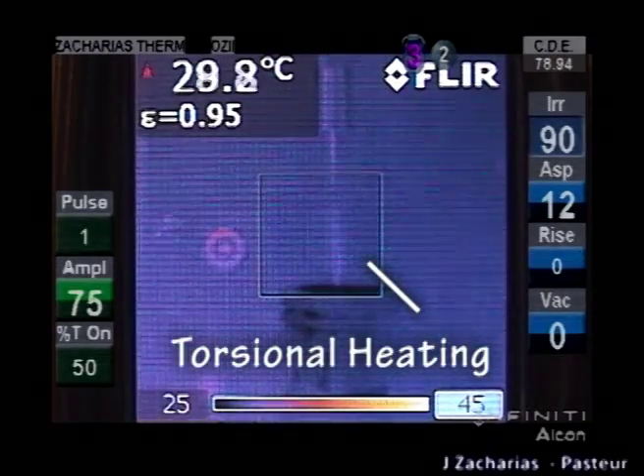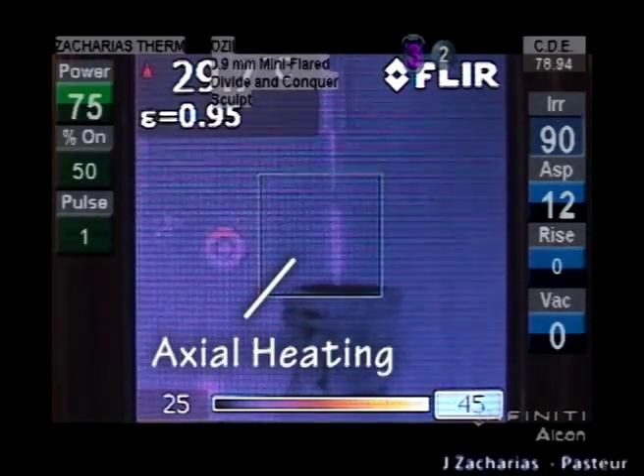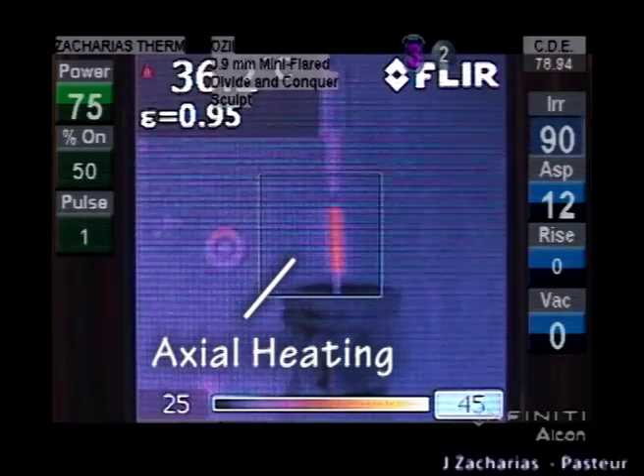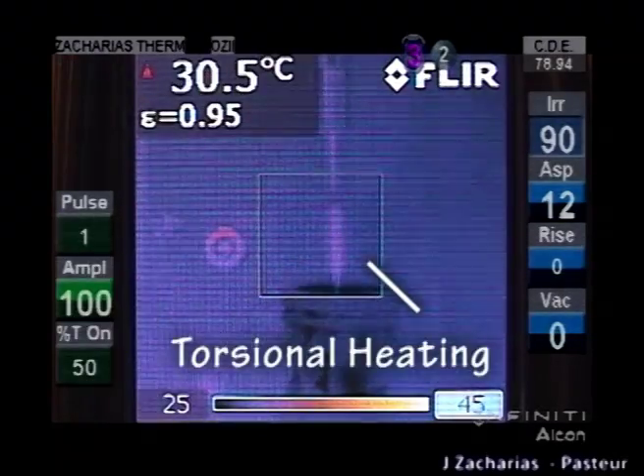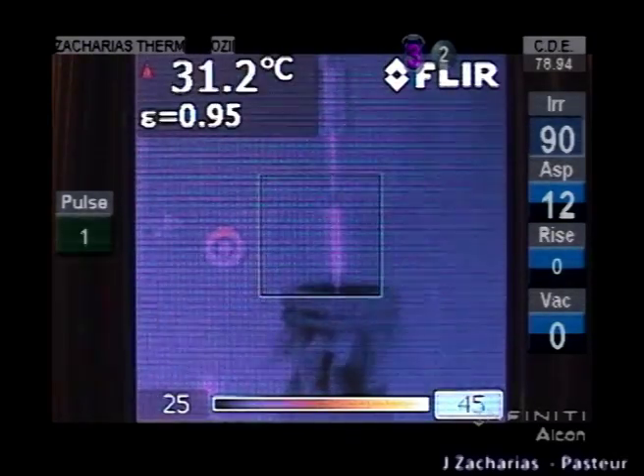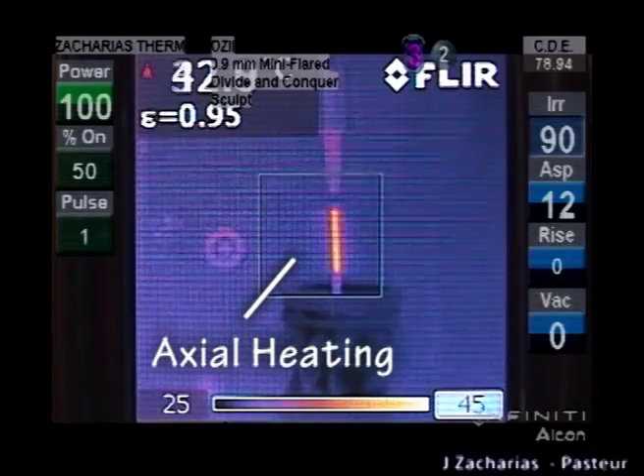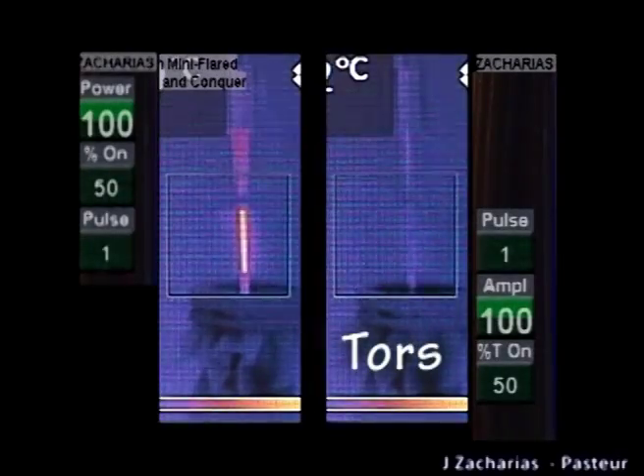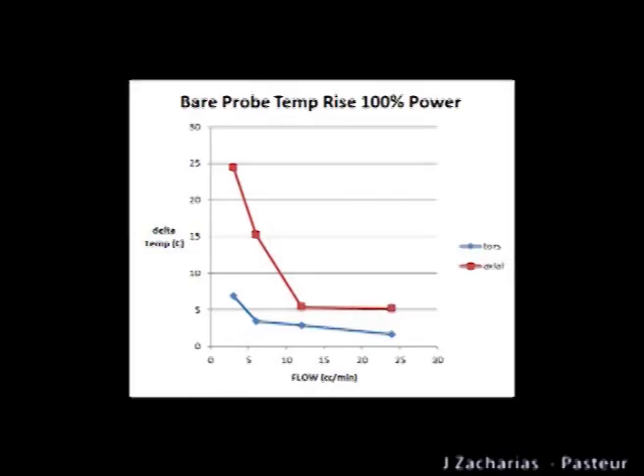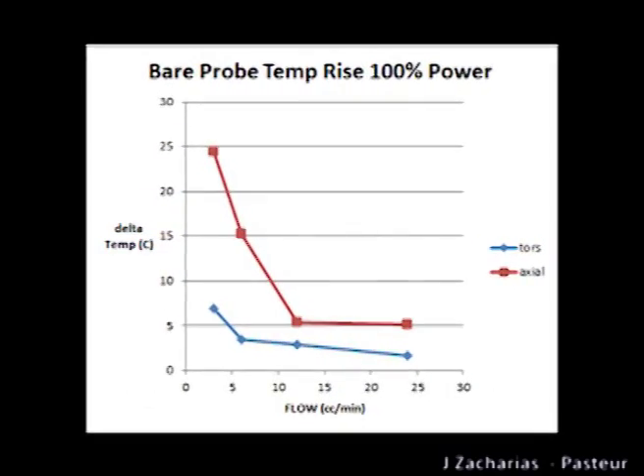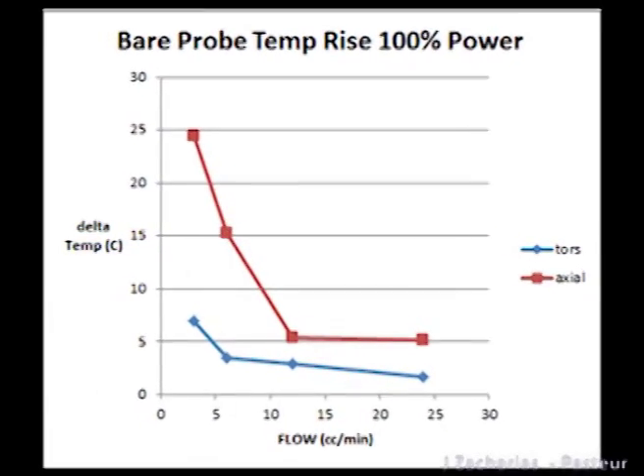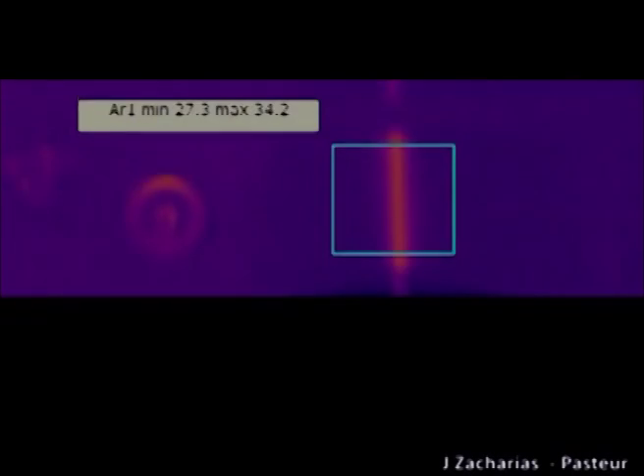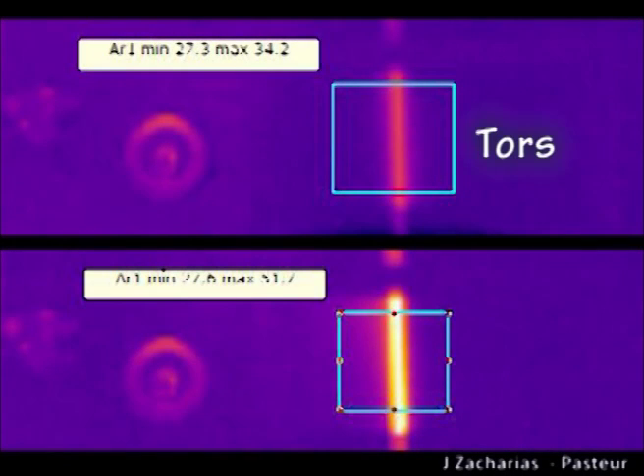Ultrasonic activation of bare probes produced an evenly distributed temperature increase in axial and in torsional modes. We were surprised to find out that torsional activation did not heat up the shaft of the bare phaco probe more than axial. High US power and reduced flow produce more pronounced temperature elevations with axial. In all tests, the probe self-heating phenomenon described was more relevant with axial operation.